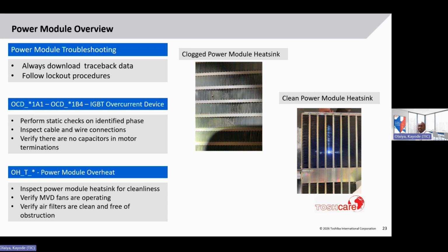So if you were to see a fault like this, after you've downloaded the traceback and locked out the drive, first thing you want to do is perform static checks on the identified phase. So if it says OCD U1A1, you want to focus on the U phase and perform the static checks I showed in the previous slide. If all the readings match the expected values, that is good news. It means that for the most part, none of the power devices are damaged. And so you now inspect and look for anything visibly out of place. Maybe a cable disconnected or fiber optic cable not secure.